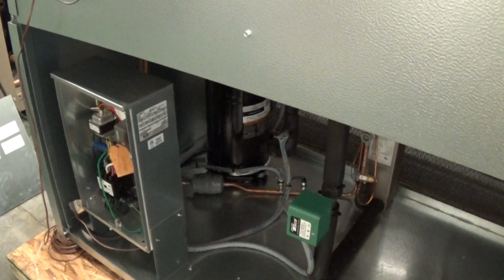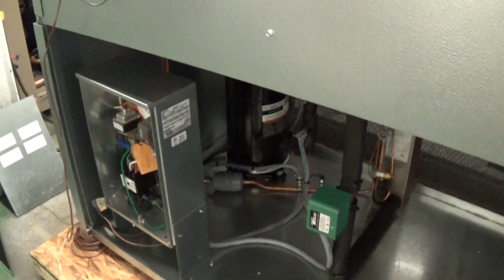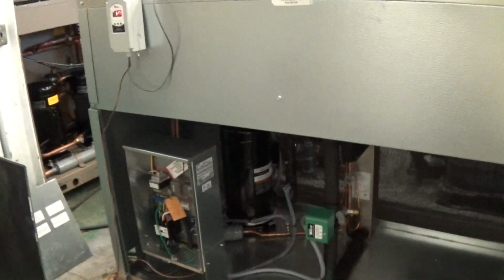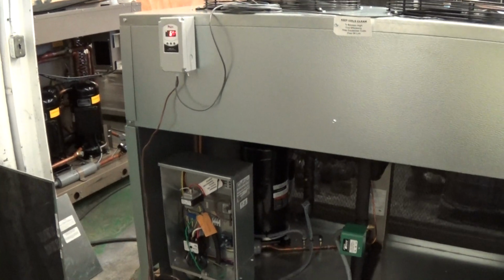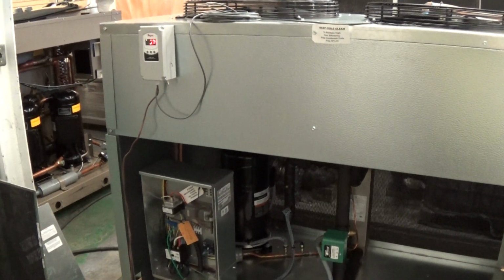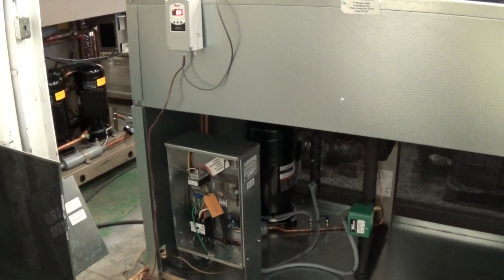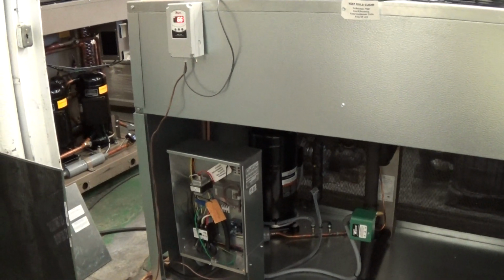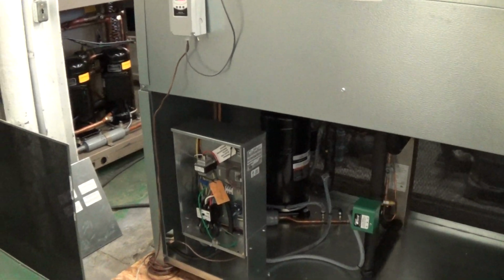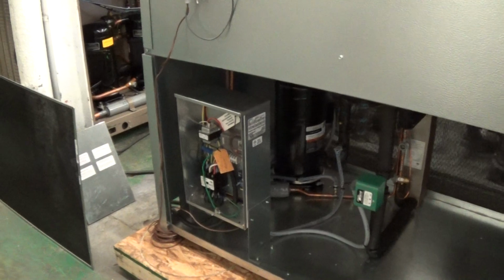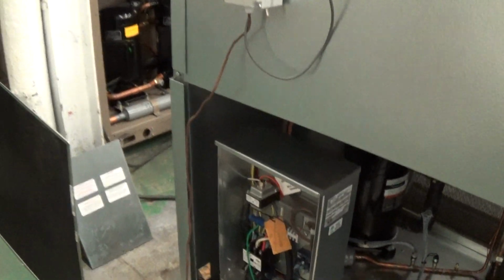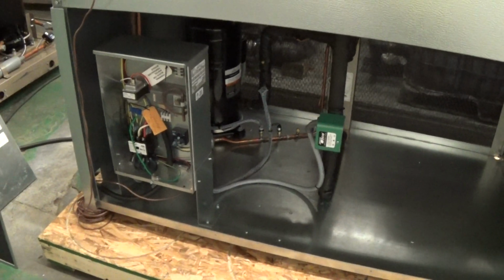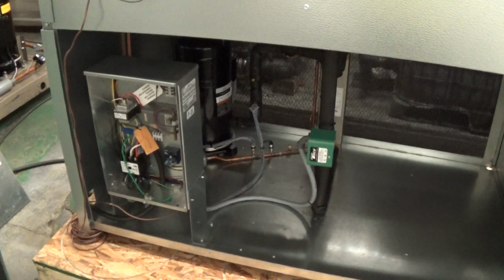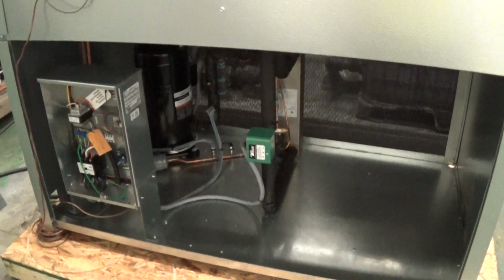You want to keep that heater band on at all times, unless you know you're going to shut it down for a prolonged period. If you do shut it down for a prolonged period, say several weeks or months, when you want to power the unit back up, let that heater band be on for about 12 hours or so before you try to turn the compressor or the chiller on by the toggle switch. Because if you don't, you can get some problems with slugging and cold refrigerant on the scroll compressor.